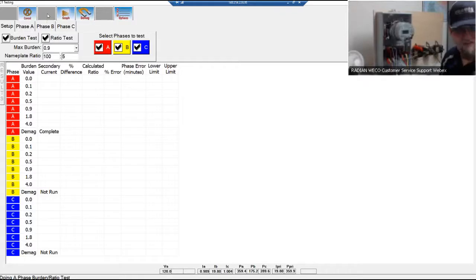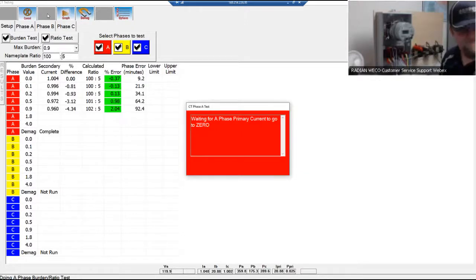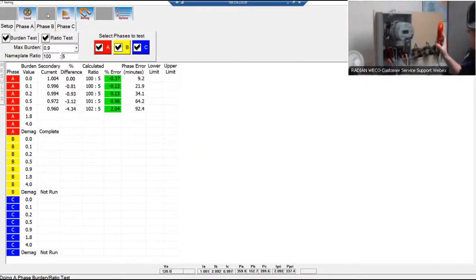You'll hear a loud beep in a second. That beep is to let you know that the CT test has been completed, and then you can move the primary probe over to your next phase. So with this, it's waiting for A phase primary current to go to 0. In other words, it's waiting for me to remove this from the primary. I've now removed that from the CT.